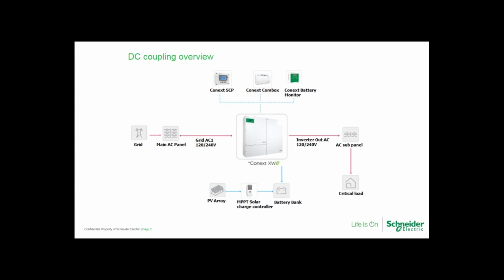When you're DC coupling, the PV supplies the charge controller, and you could have multiple charge controllers, each with their own dedicated array, which in turn regulates to the battery and prevents overcharging. Once the battery's full, the battery voltage is reduced to a float level, which means it's being trickle charged. Solar energy will be used to support the load using the residual of charge current. In other words, during the bulk state, 100% of the PV power is being used to charge the battery.